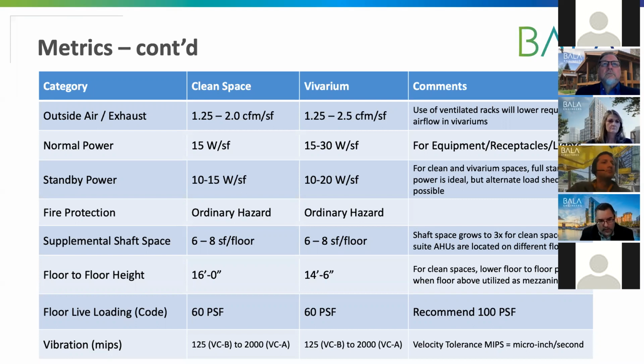With the vivarium, it's a little bit different in that the variations you see here are based on the animals that will be housed. So your larger animals, canine and swine, will be on the larger end of 2.5 CFM. Your smaller or rodent animals will be on the lower end, the 1 to 1.25 CFM. And even further reductions can be had with vivarium if you utilize a ventilated rack system to house the rodents.